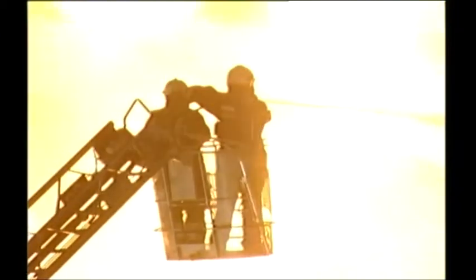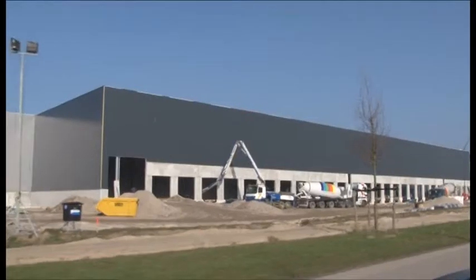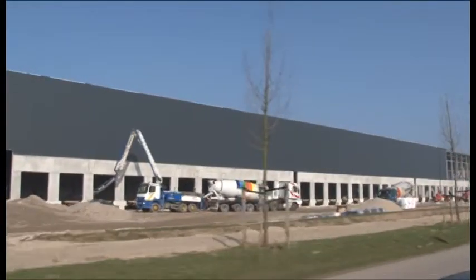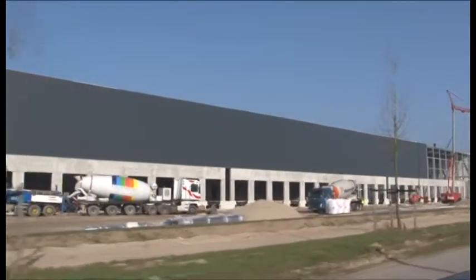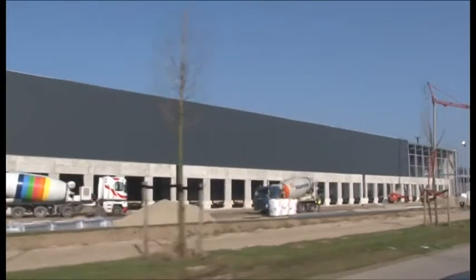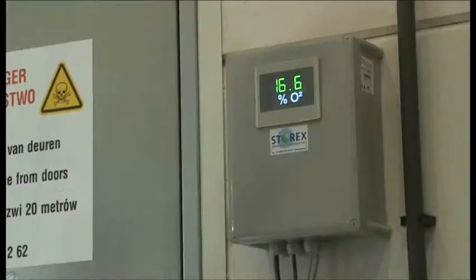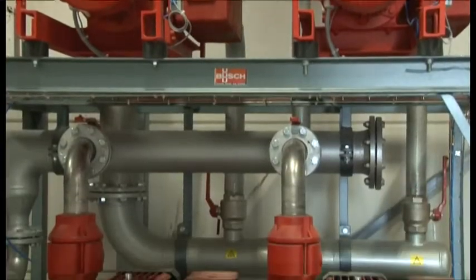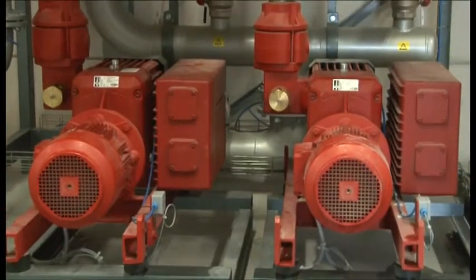You could take away the oxygen considerably — but how? That has been considered and is applied for the first time in the Netherlands in the warehouses for cocoa products of DSV in Amsterdam. The oxygen percentage, normally 21% or more, is brought back to a value of between 16 and 17%. Generators introduce nitrogen to do this job, and smouldering is prevented.